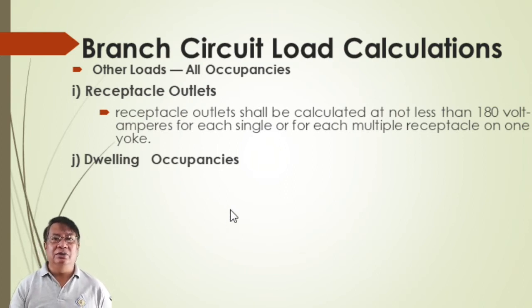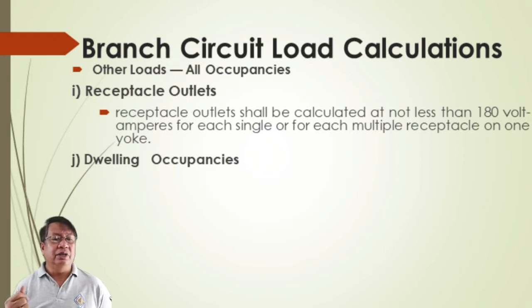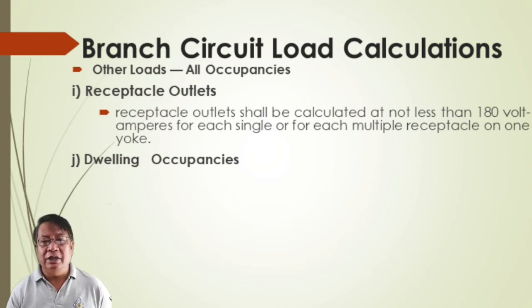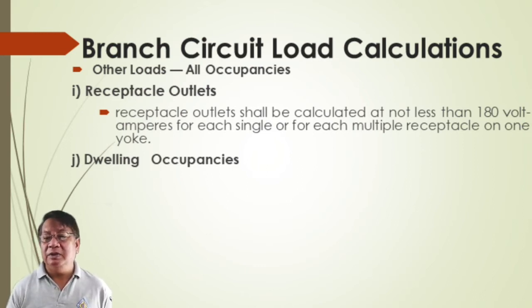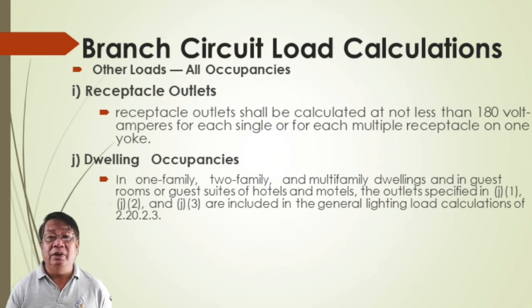If you can determine where to place your outlets, count how many outlets you have, then consider 180 volt-amperes for each outlet as the considered load in that specific branch circuit. For dwelling occupancies — one-family, two-family, and multi-family dwellings — consider 2.20.2.3 calculations.